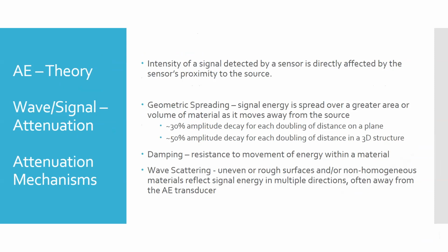I've got amplitude decay for doubling a distance on a plane. So if you have a fairly flat piece of material, each time you double the distance, the energy is going to be reduced by approximately 30%. It depends on the exact attenuation level of the material, but on average, 30% amplitude decay for each doubling of distance. If you're in a three-dimensional structure, that becomes a 50% decay, because we're spreading that energy through a larger and larger volume of material as we go further away.